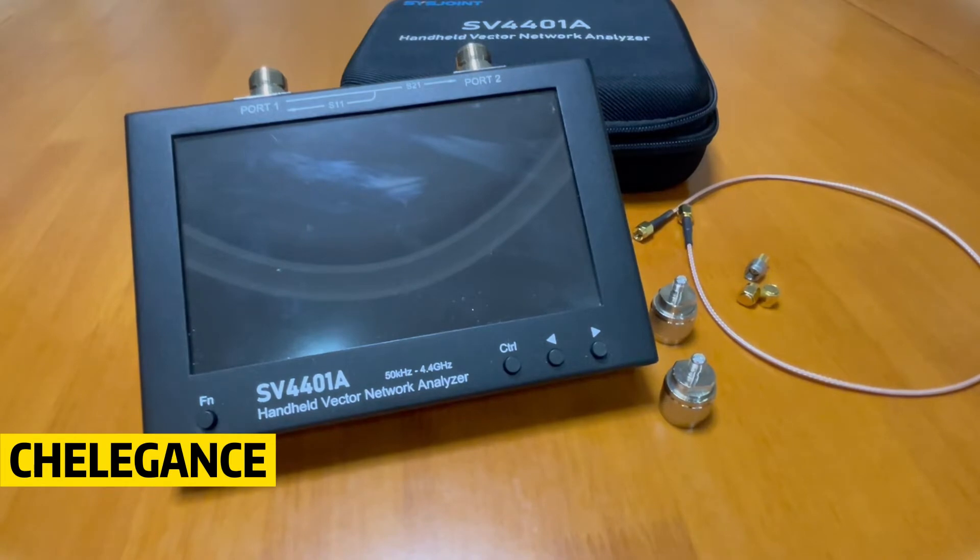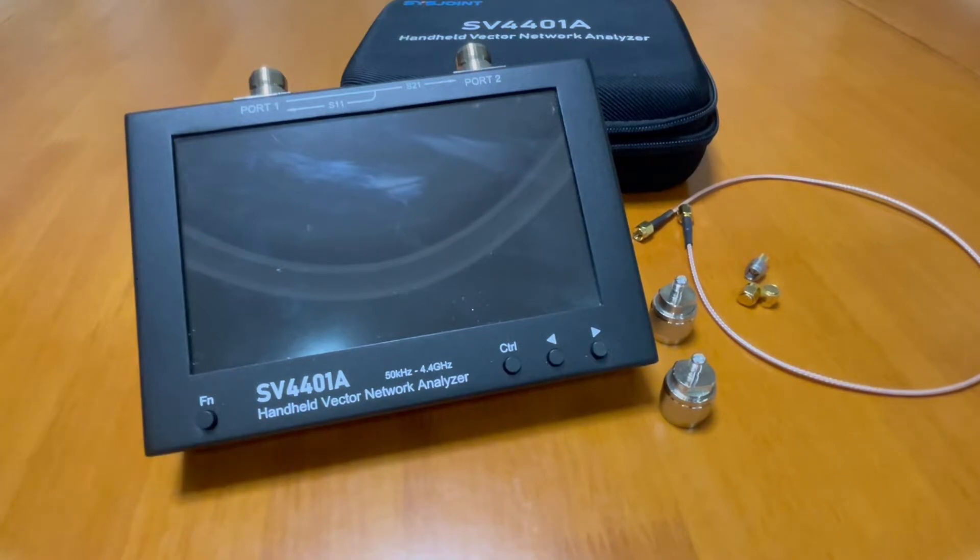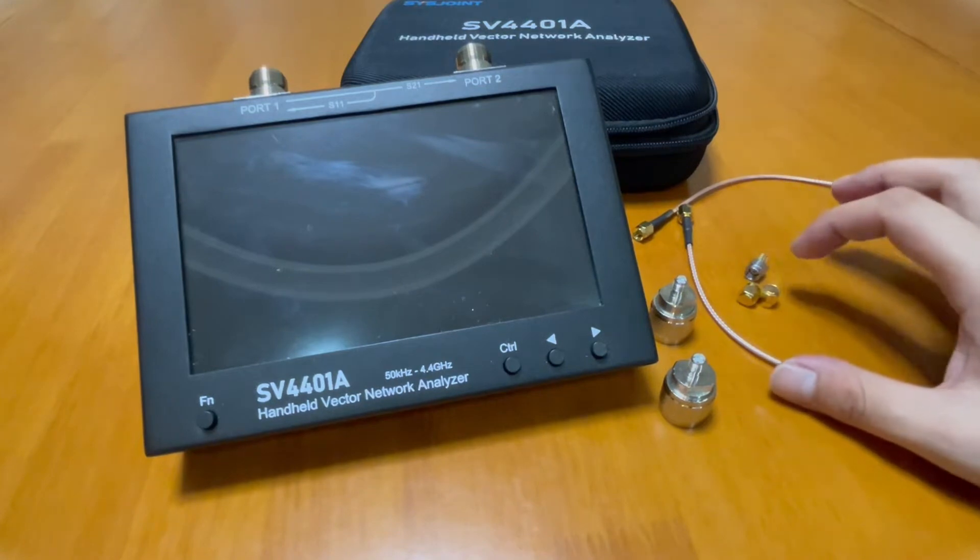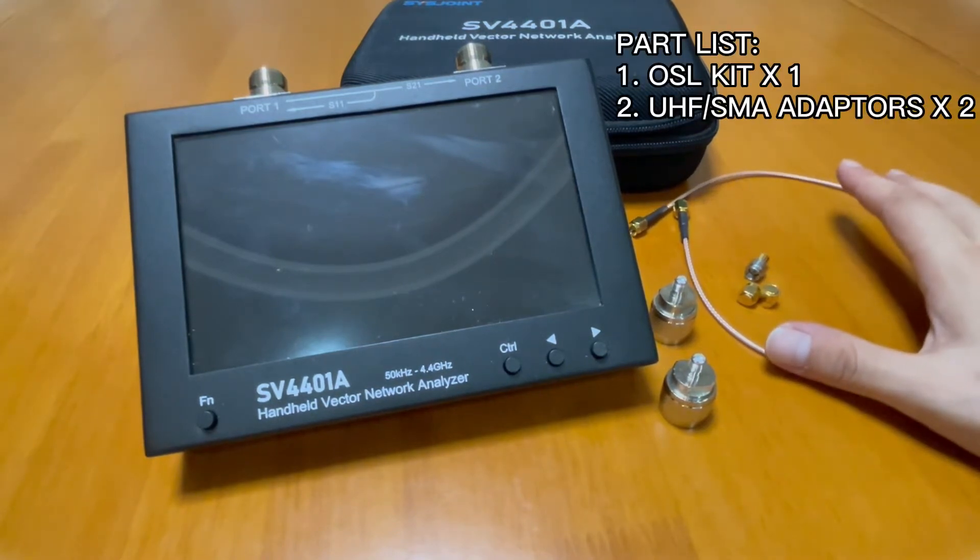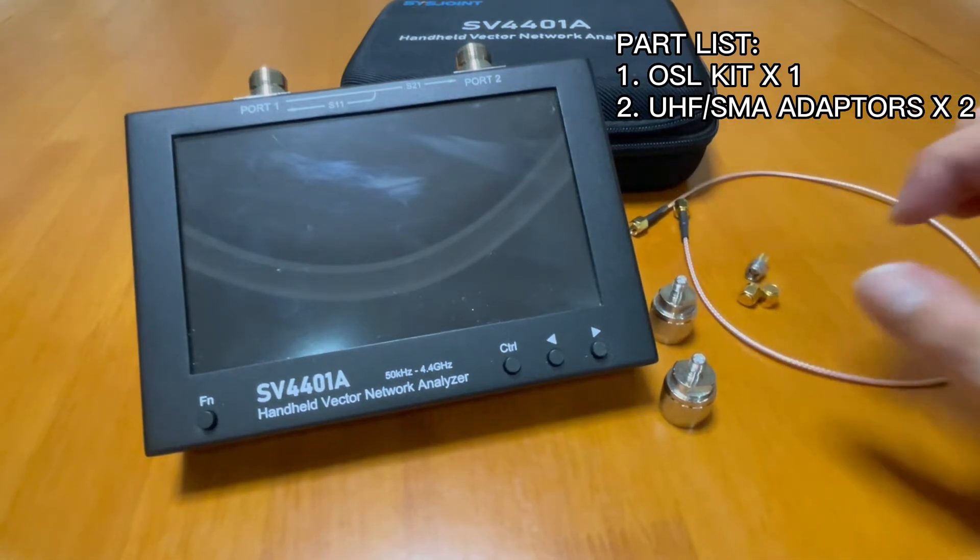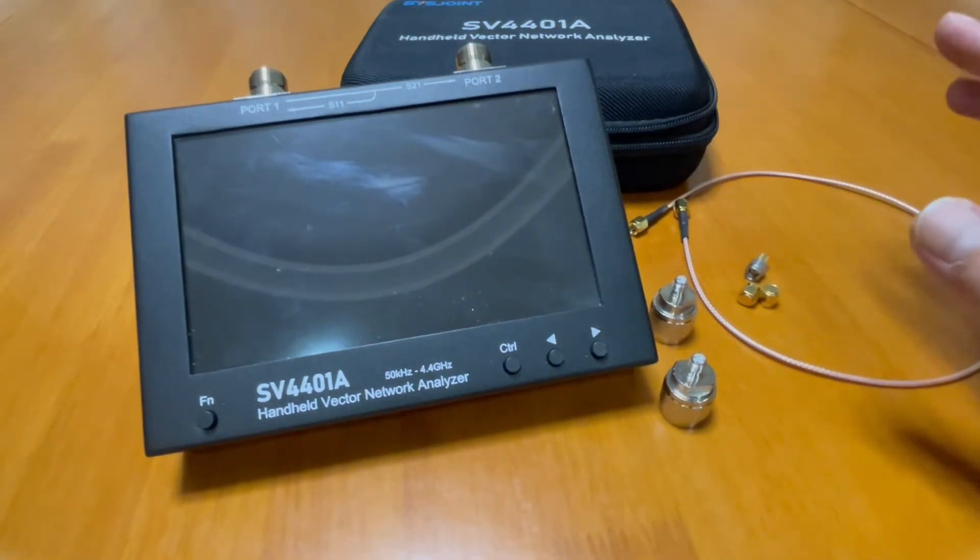To perform a calibration on the SV4401A is quite easy. The first thing you want to do is check if you have everything that you need. The OSL calibration kit means the open, short, and load, one cable, and what you need is two adapters. All the things that you need come right out of the kit that you buy.